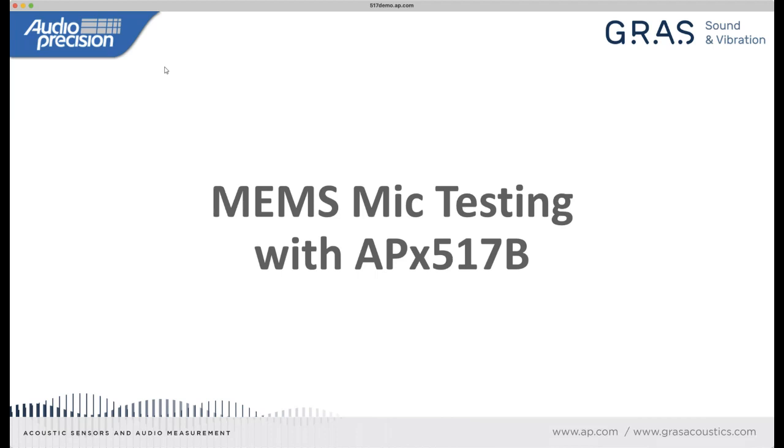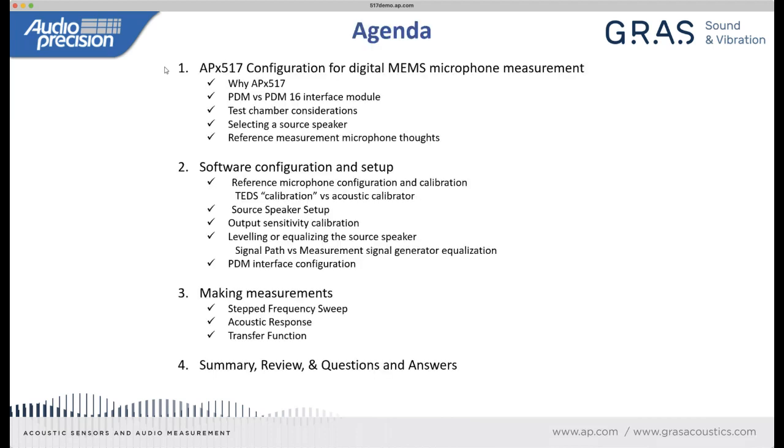All right, thank you, Paige, and good morning, good afternoon, or whatever time zone you may be. Welcome. So in this hour, I'm just going to go over really the practical side of measuring a MEMS microphone with a PDM output. We do generically assume that a MEMS microphone has a PDM output, and that's what we'll be demonstrating today. But there are MEMS microphones with analog outputs and MEMS microphones with I2S outputs, and those would have some slightly different physical configurations.